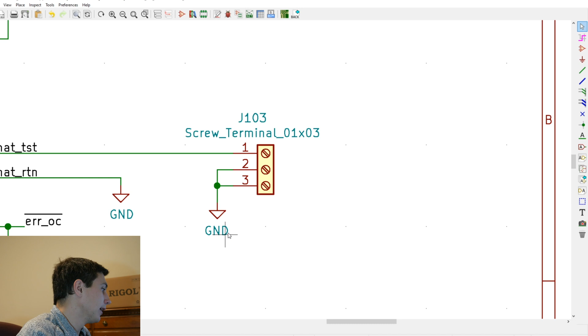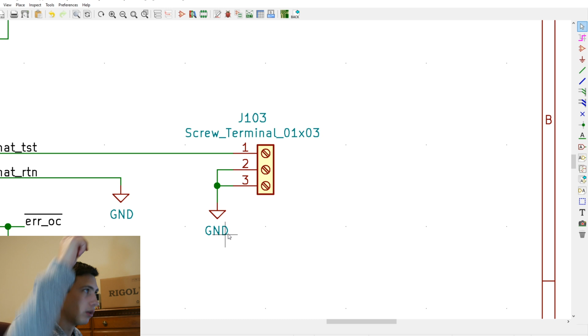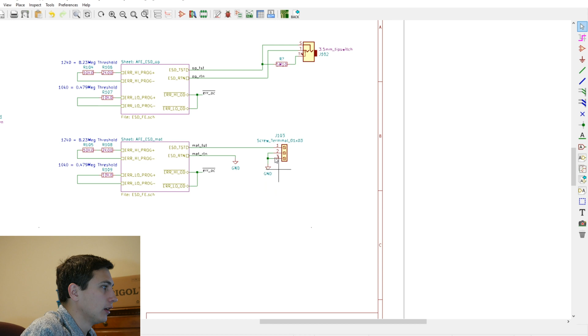So what I'd recommend is that you take one of these blocks, tie it to ground, and then have a separate path to ground through your ESD mat—then you're checking that whole loop back through your grounding strip, the ground terminal of your power strip, and the ground wire through your wall. You end up testing that connection all the time.